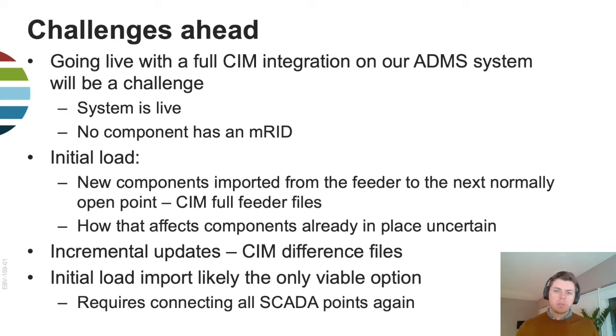The system also uses CIM difference files for incremental updates. A CIM difference file is some CIM XML. It includes all the changes made in the representation of a part of the grid. For example, if you were to cut the cable to introduce a new substation, then the original cable is listed as deleted, two new cables will be listed as new, and the substation, including all the equipment, will be listed as new. The CIM difference file includes both backwards differences, as in how it was before, and forward differences, as in how it is going to become.